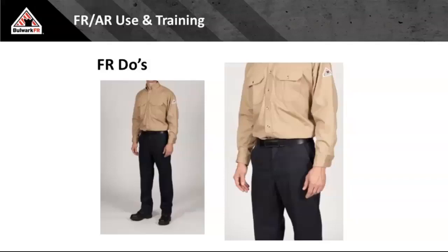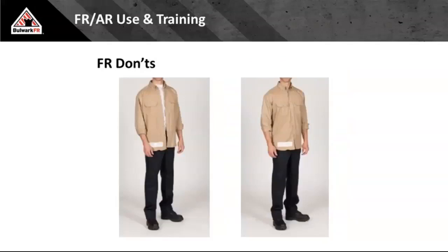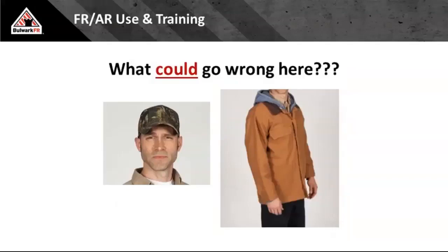It comes up the pant leg. And if you are unbloused, if you are sitting outside of your belt line, it will lift up that fabric and it will send all that energy underneath. And if you happen to be either A, not wearing anything, or B, wearing a lightweight cotton t-shirt, or C, worse, a synthetic, it will cause potential injury that need not happen because why? It wasn't deployed properly. This is what we see in the field far too often. And the excuse is, hey, I'm not working energized right now, okay? But what's going to happen when you do go to do energized work and you forget?